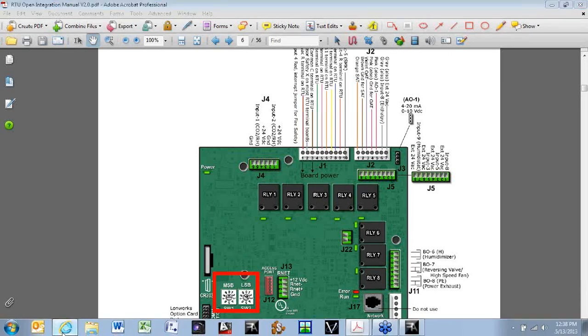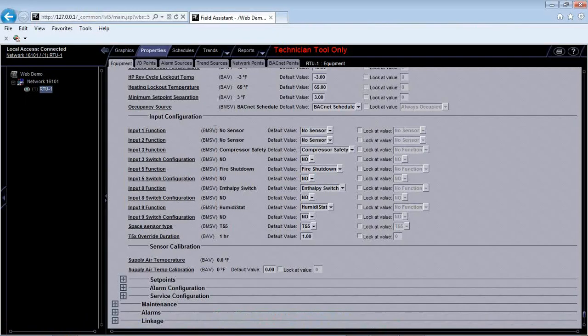Okay, so if I go back to our field assistant here, input 1 has a couple different options of what you can wire in. Okay, you can wire in an indoor air quality sensor, an outdoor air quality sensor, or a space relative humidity sensor. Those are the only 3 options you can wire into that specific input. That's just how the controller is configured and programmed from the factory. Those are your only options. So for an IAQ sensor, that would be an indoor CO2 sensor. An OAQ sensor would be an outdoor CO2 sensor, and then space relative humidity would be space humidity.